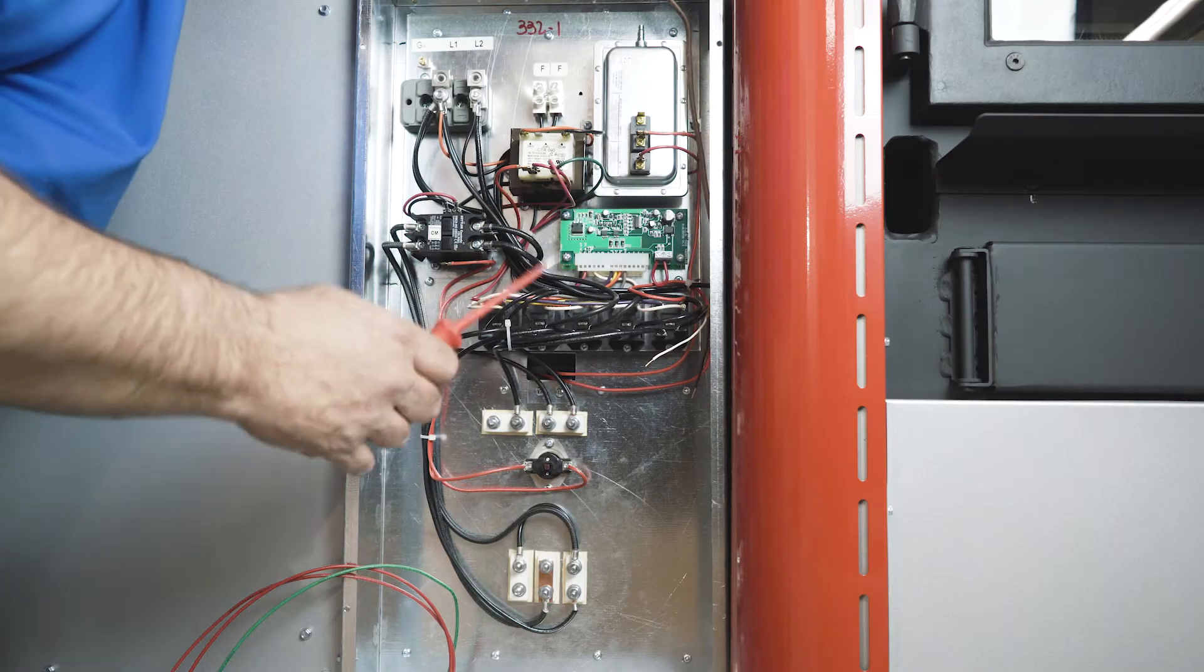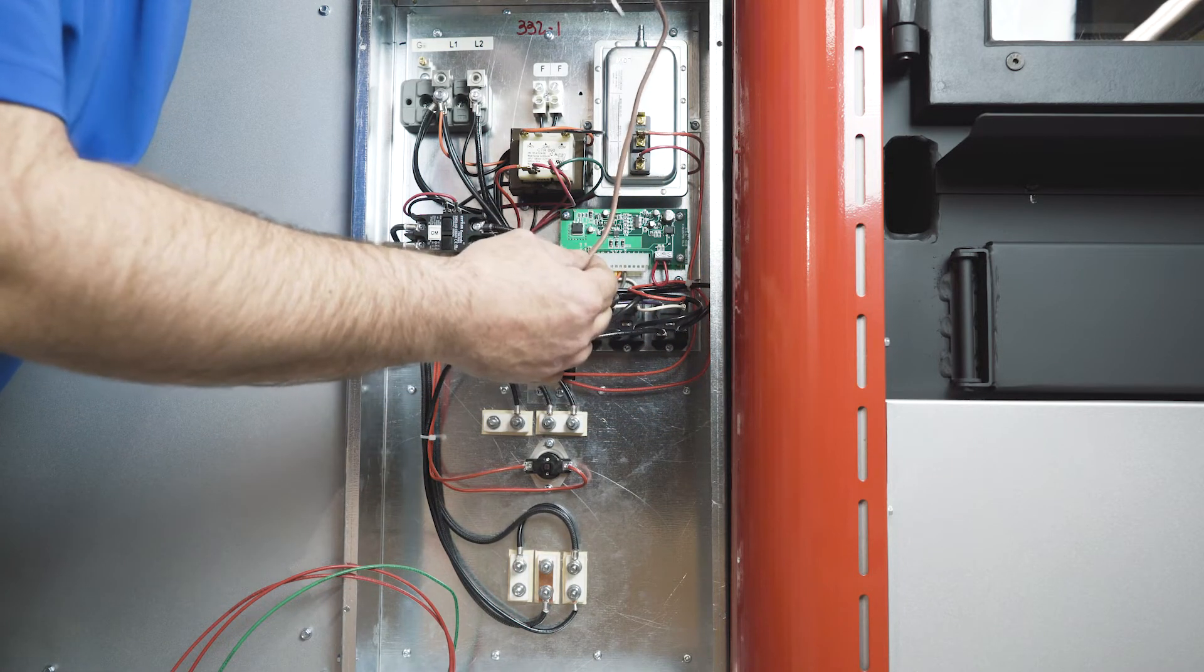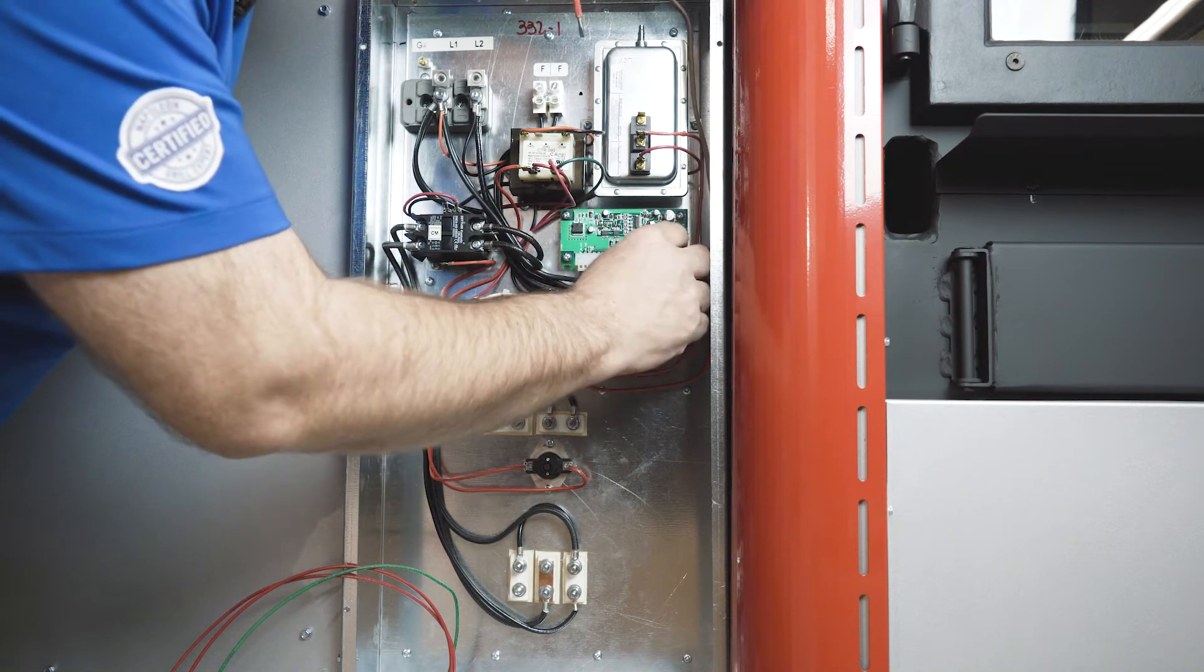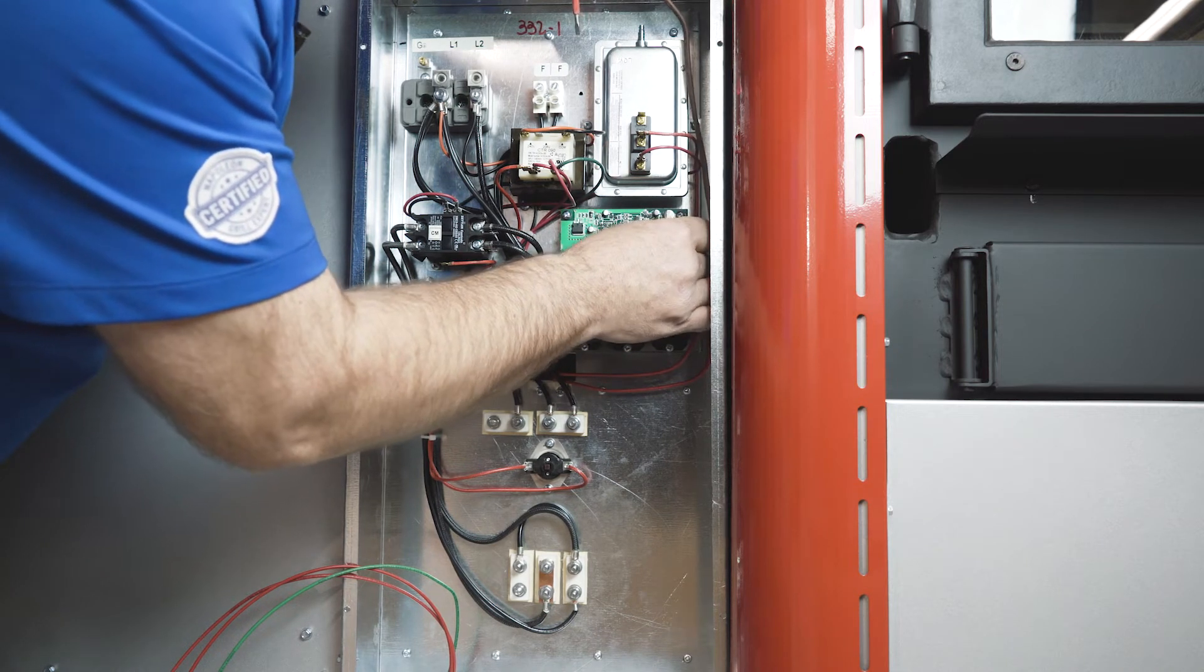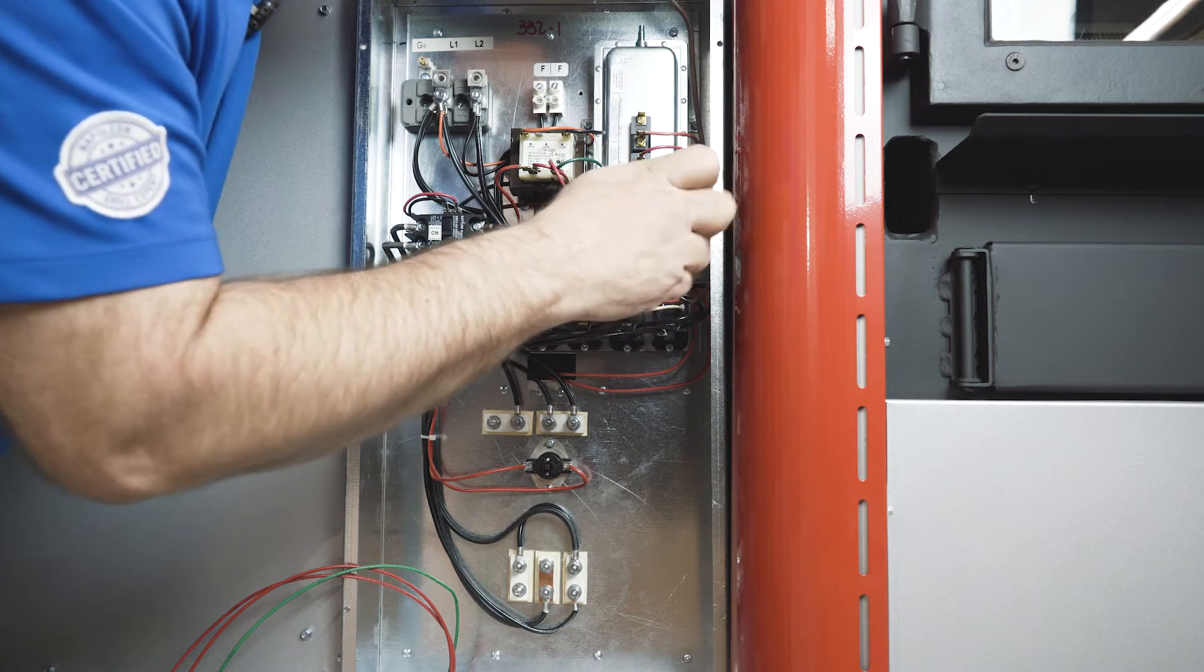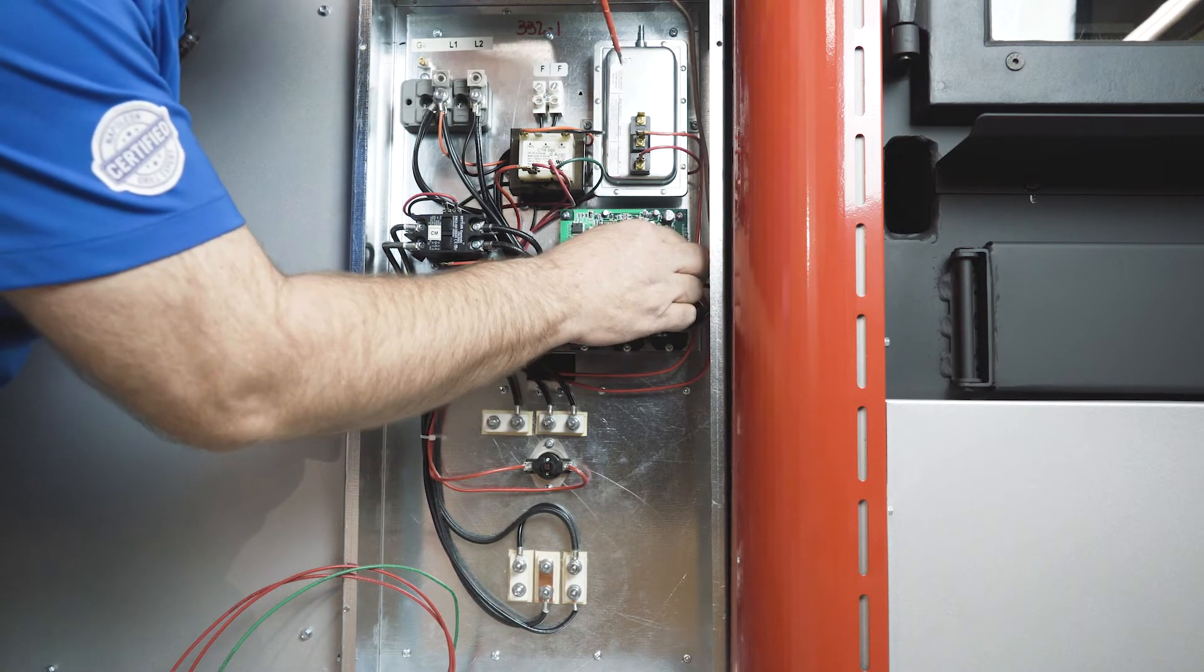So we're here at our fan module. We've got our wiring, and again this wire comes from the 4 and 7. We need to run it over here to the common on the board. Please do not remove the jumper. You do need that in place for proper operation.